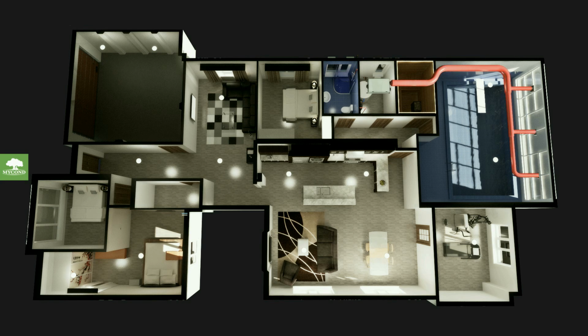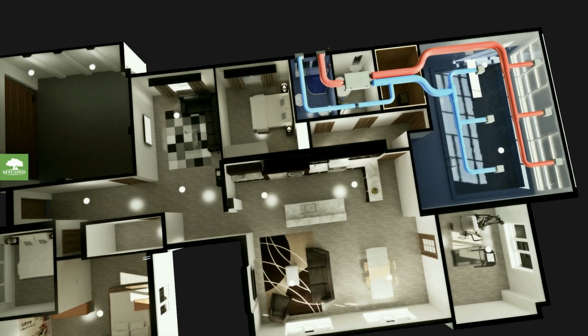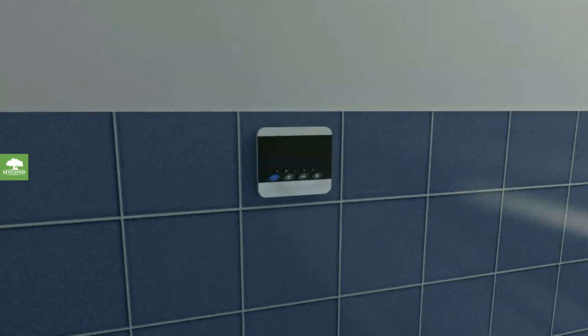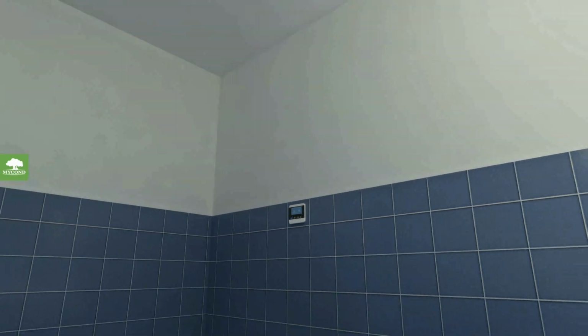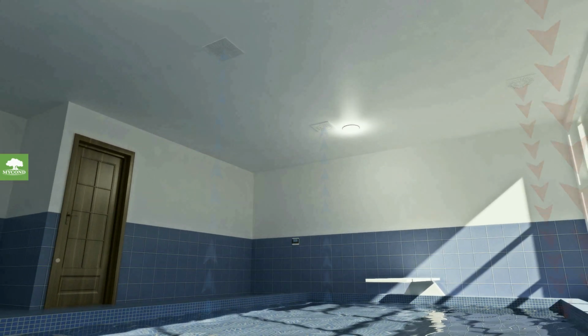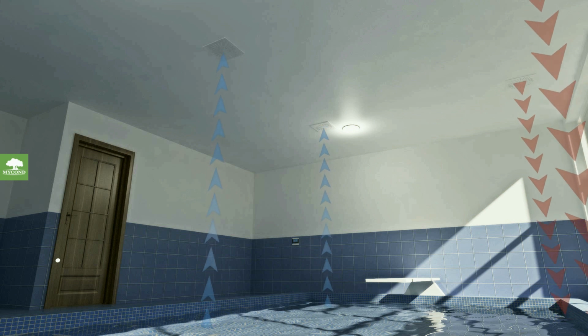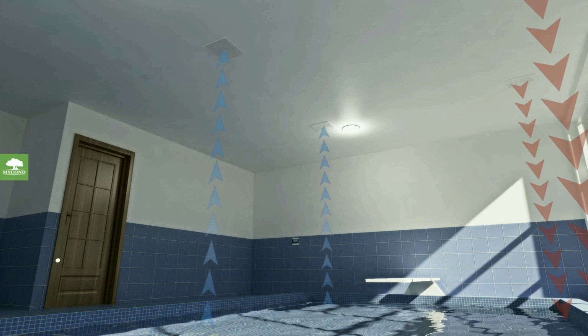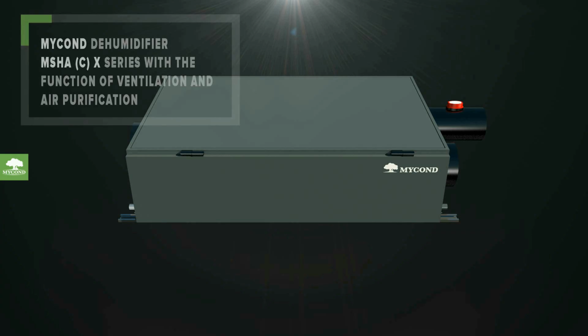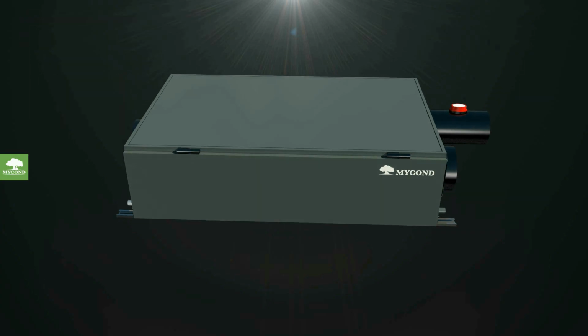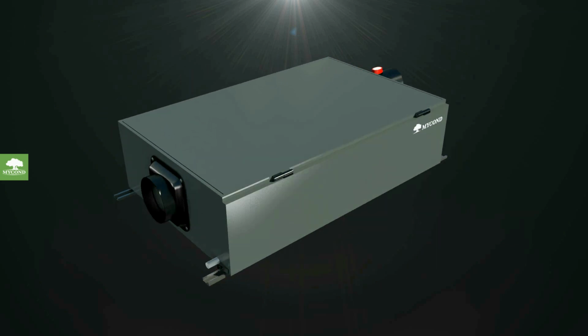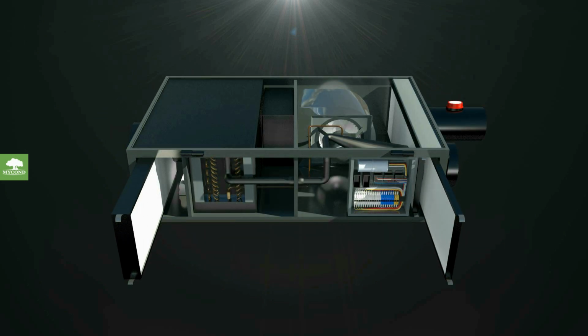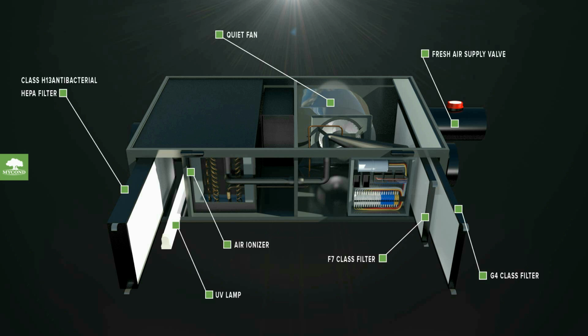Mycond duct dehumidifiers are a comprehensive solution for maintaining humidity in the pool, ventilation and air purification. Dehumidifier is installed in a technical room and is connected with the pool premises by a network of air ducts. Dehumidifier's operation is managed via the controller installed in the premises of the pool. Mycond dehumidifier with ventilation and air purification function has 3 G4 and F7 filtration classes, as well as an antibacterial HEPA filter of class H13. An ultraviolet lamp and air ionizer are built into the dehumidifier.